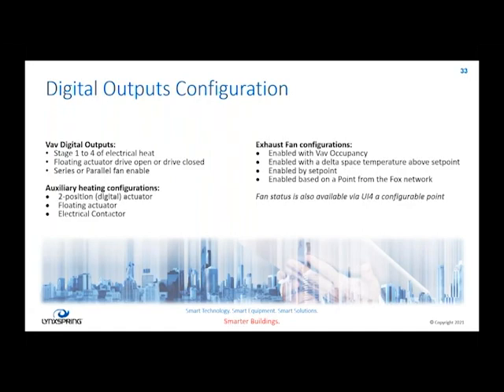Our digital outputs, because they're configurable, you can have up to 4 stages of electric reheat. You can do floating actuators. You can do drive open, drive closed. If your VAV has a drive open and drive closed, and your auxiliary heat has a drive open, drive closed, we can support that. We can do series parallel fan. And the great thing is because these are configurable, if the electrician goes out there and lands the fan on DO1 and stage 1 on DO2, but they were backwards, you can easily reconfigure your VAV on the fly to make it fit the configuration. Electricians are notorious for getting drive open, drive closed backwards on a reverse actuator. So you can easily change those with the configurable digital outputs.